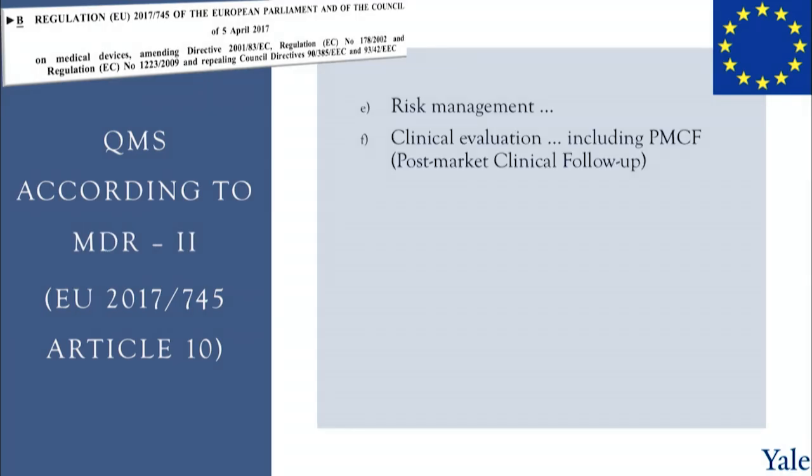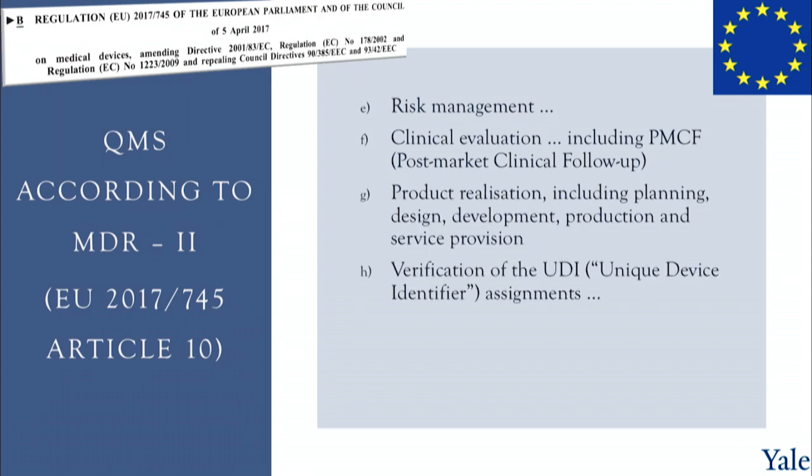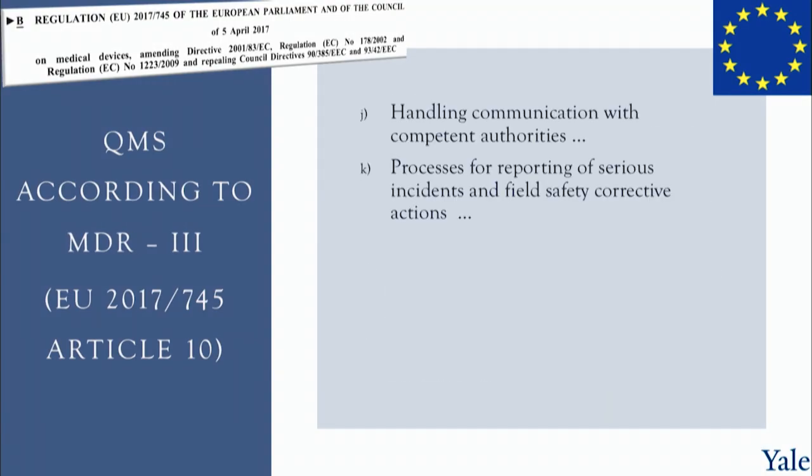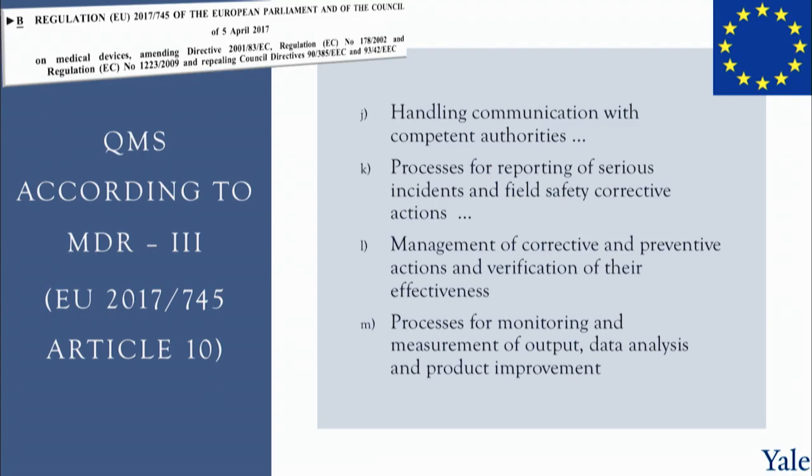Risk management, clinical evaluation, including critically PMCF, post-market clinical follow-up. Product realization, including planning, design, development, production, and service provision, verification of unique device identifiers, setting up implementation and maintenance of post-market surveillance systems, and the list goes on to handling communication with competent authorities, the government agencies that monitor you, processes for reporting of serious incidents and field corrective actions, management of corrective and preventative actions and verifications of their effectiveness, and then the final step, processes for monitoring and measurements of outputs, data analysis, and product improvement.